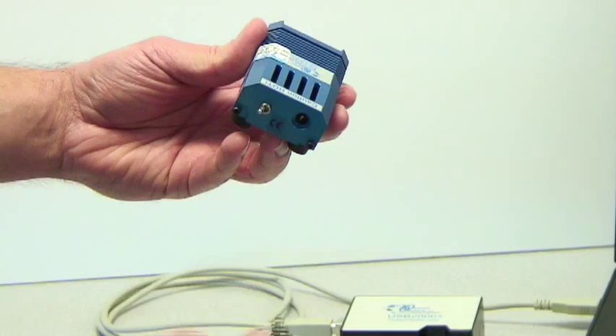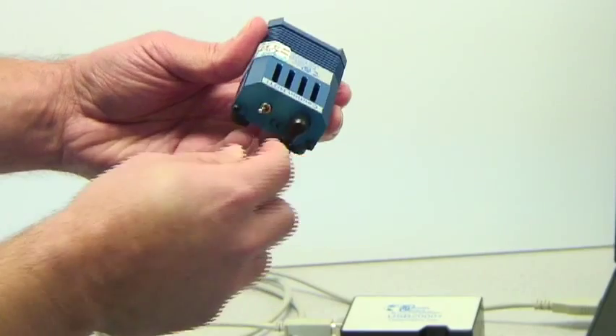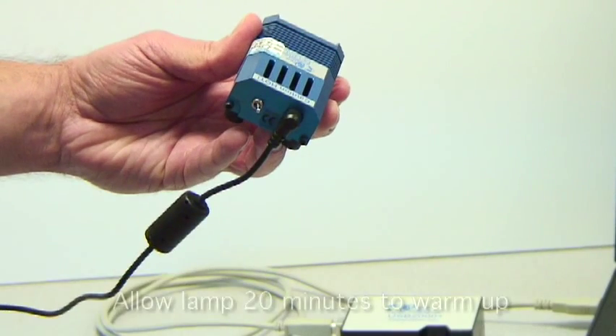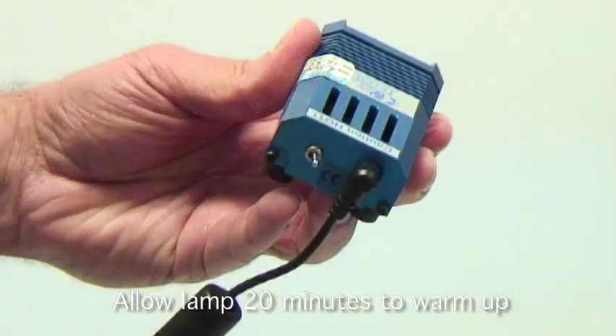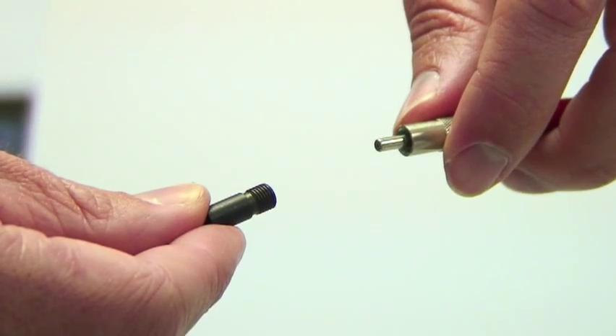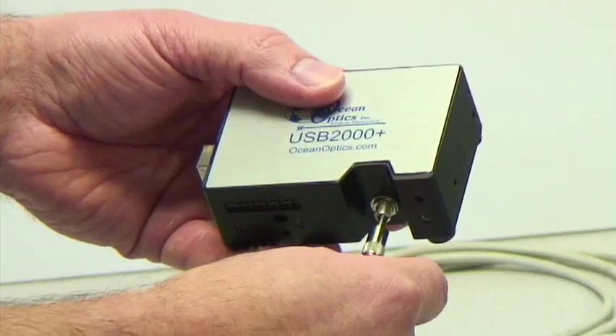First, you should connect the power to the light source and turn it on so that it can begin to warm up. For the LS-1-CAL, it is recommended to let the lamp warm up for at least 20 minutes. Next, connect one end of the patch cable to the cosine corrector. Connect the other end of the patch cable to the SMA connector of the spectrometer.